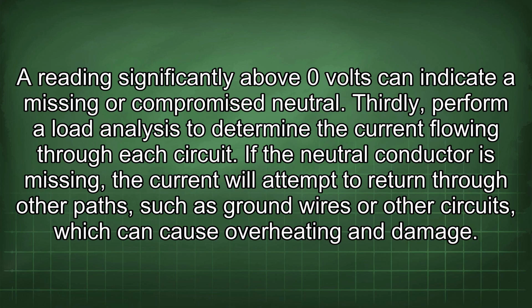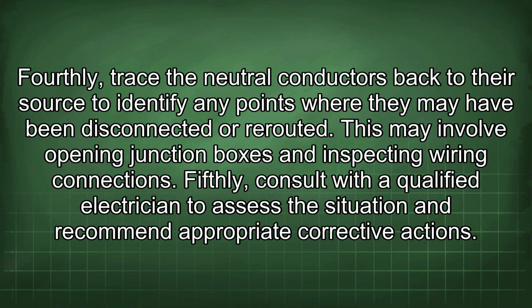Thirdly, perform a load analysis to determine the current flowing through each circuit. If the neutral conductor is missing, the current will attempt to return through other paths, such as ground wires or other circuits, which can cause overheating and damage. Fourthly, trace the neutral conductors back to their source to identify any points where they may have been disconnected or rerouted. This may involve opening junction boxes and inspecting wiring connections.